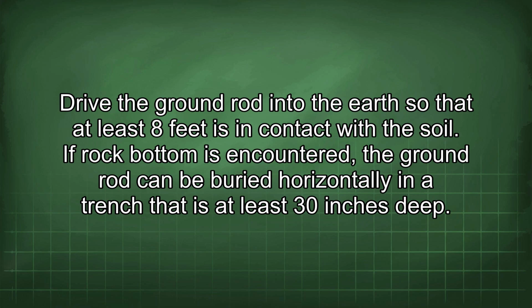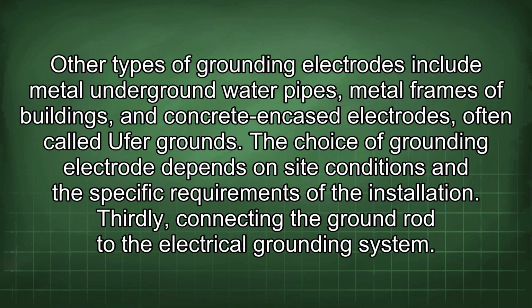If rock bottom is encountered, the ground rod can be buried horizontally in a trench that is at least 30 inches deep. Other types of grounding electrodes include metal underground water pipes, metal frames of buildings, and concrete encased electrodes, often called UFER grounds. The choice of grounding electrode depends on site conditions and the specific requirements of the installation.